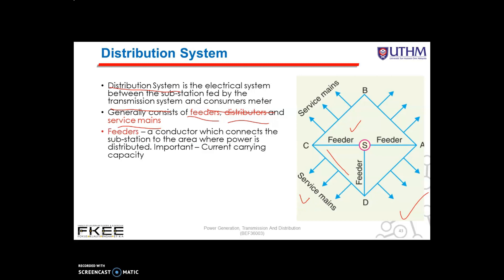The first one is feeders. A feeder is a conductor which connects the substation — S is the substation — or localized generating station to the area where power is to be distributed. From the substation to the distributors, we have the feeder. Generally, no tapings are taken from the feeder, so the current remains the same throughout. From the substation to the distributors, there is no tapping at the feeders.